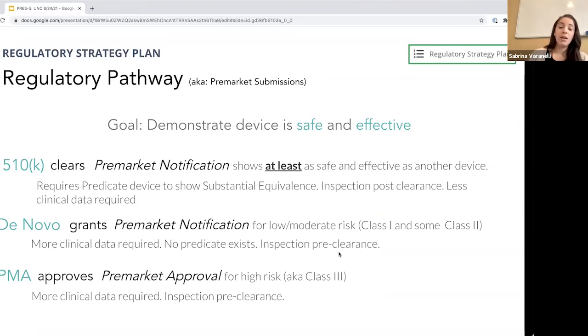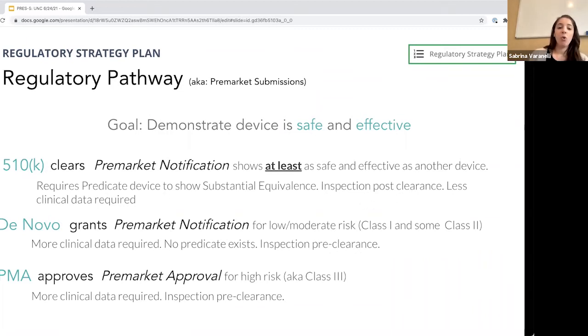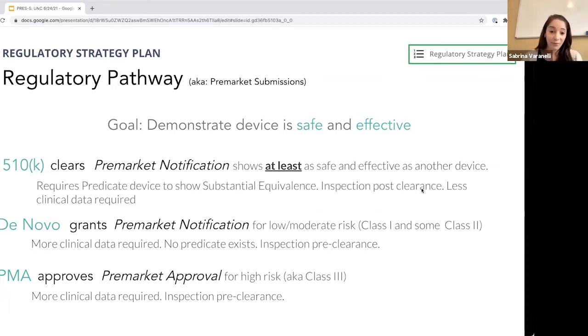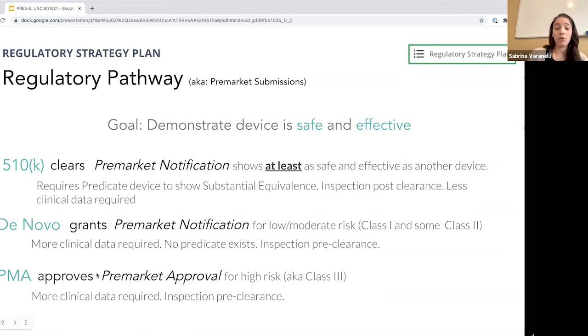From a timeline perspective, this is very critical to know upfront. The FDA gives you three 90-day review cycles from the day you submit your application — so it could take up to three quarters before you're allowed to sell your product, if you're a 510k, since you can get your inspection after clearance. For a DeNovo or PMA, you have to be inspected before clearance, so that three quarters could drag to four or five quarters depending on how busy the FDA is — that's a whole year of runway to plan for. Not knowing this when raising venture capital is a serious planning issue.